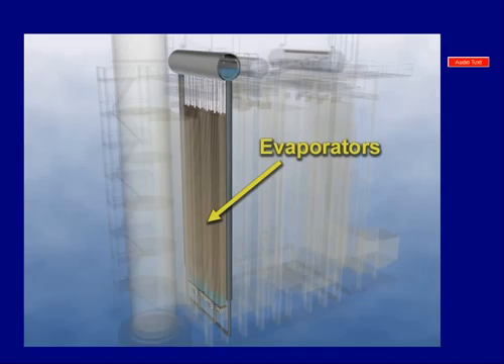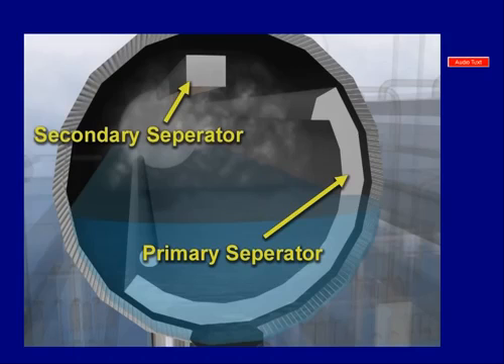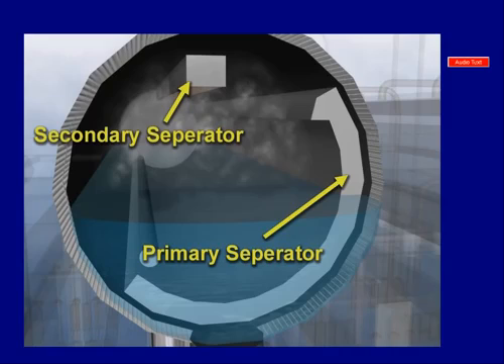As this steam-water mixture enters one of the three drums, it first passes through the primary steam separator, where water and steam are separated. Before leaving a drum, the steam passes through the secondary separator and leaves the drum through a saturated steam line.